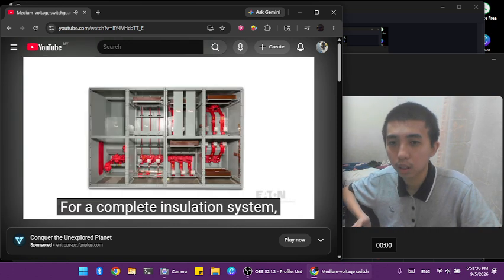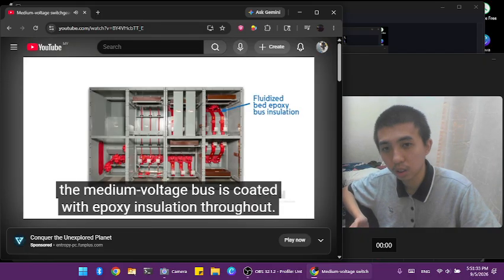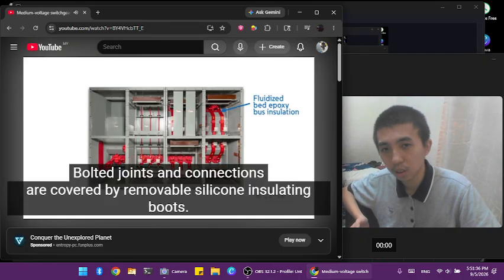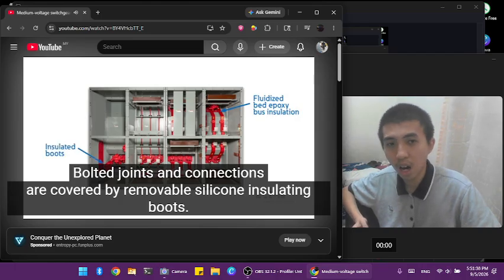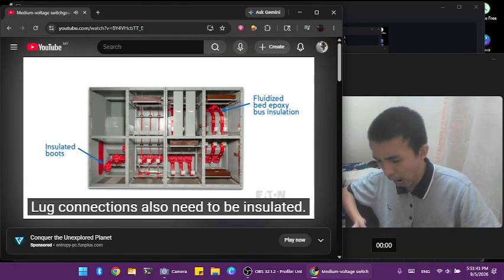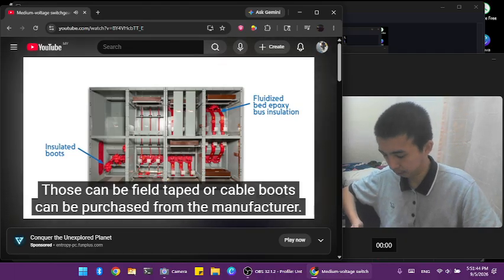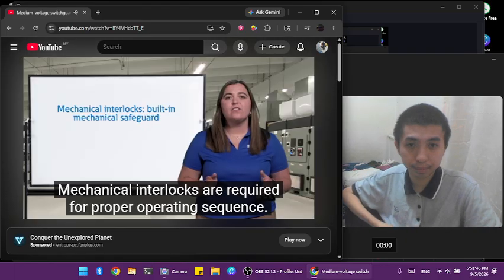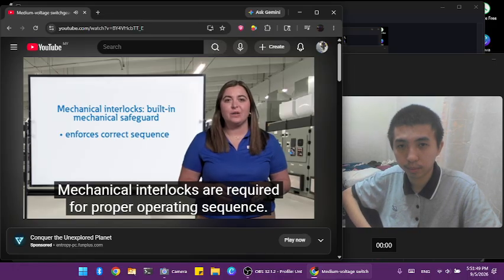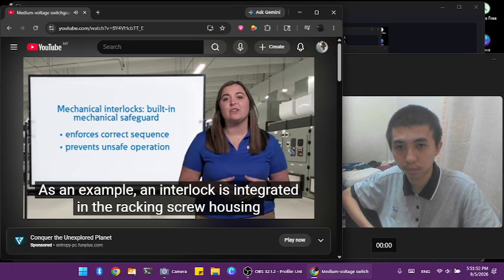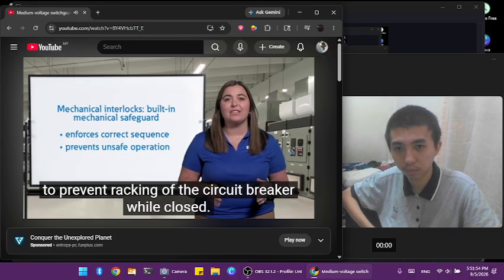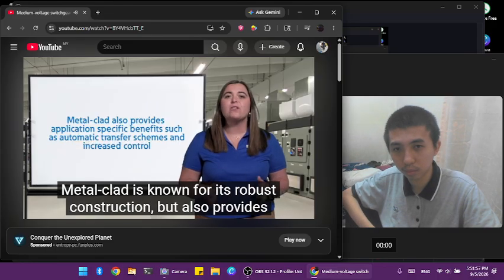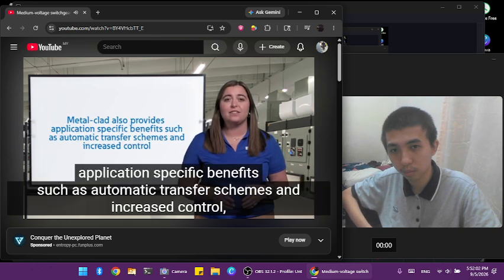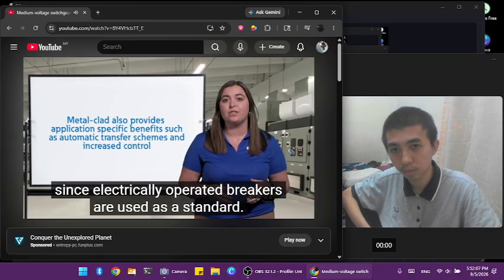For a complete insulation system, the medium voltage bus is coated with epoxy insulation throughout. Bolted joints and connections are covered by removable silicone insulating boots. Lug connections also need to be insulated. Those can be field taped or cable boots can be purchased from the manufacturer. Mechanical interlocks are required for proper operating sequence. As an example, an interlock is integrated in the racking screw housing to prevent racking of the circuit breaker while closed. Metal-clad is known for its robust construction, but also provides application-specific benefits, such as automatic transfer schemes and increased control, since electrically operated breakers are used as a standard.